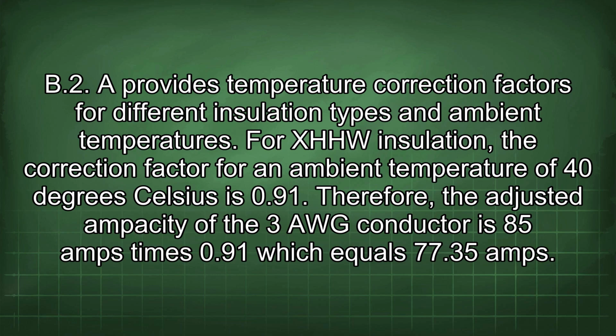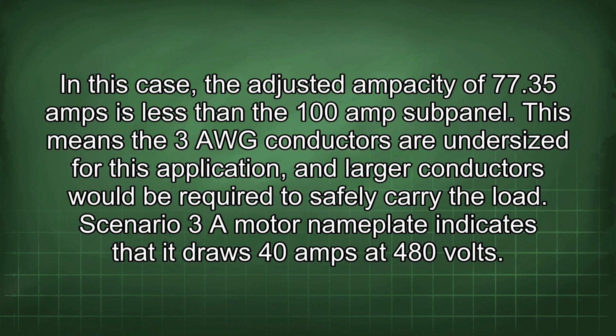Therefore, the adjusted ampacity of the 3 AWG conductor is 85 amps times 0.91, which equals 77.35 amps. In this case, the adjusted ampacity of 77.35 amps is less than the 100 amp subpanel. This means the 3 AWG conductors are undersized for this application, and larger conductors would be required to safely carry the load. Scenario 3, a motor nameplate indicates that it draws 40 amps at 480 volts.